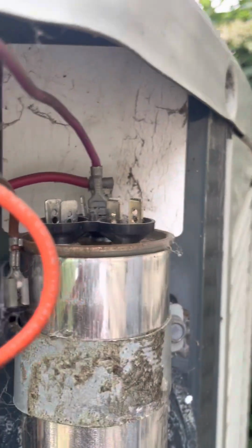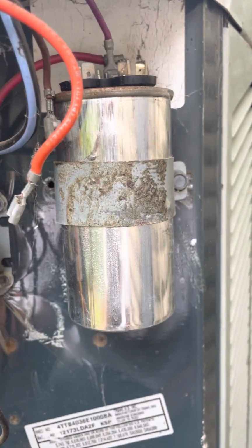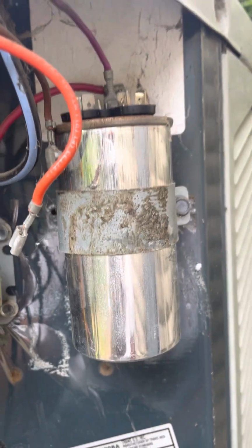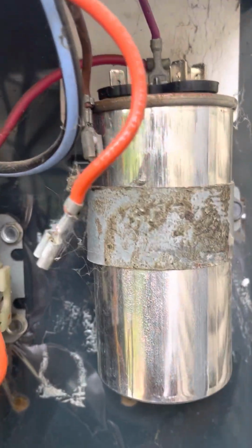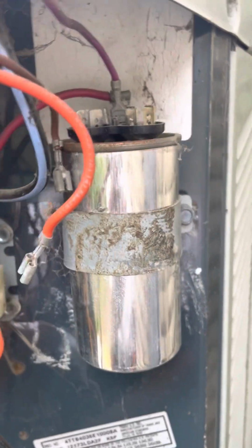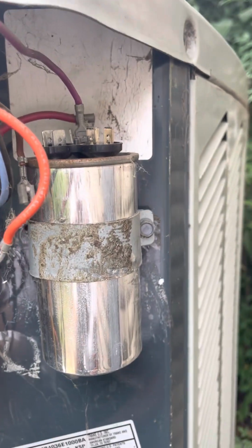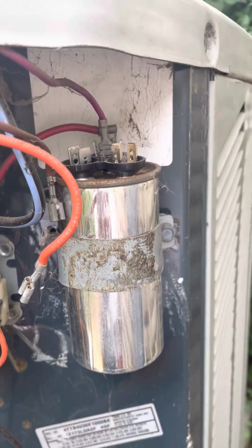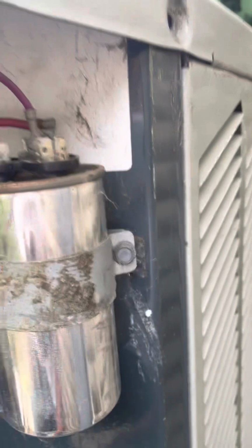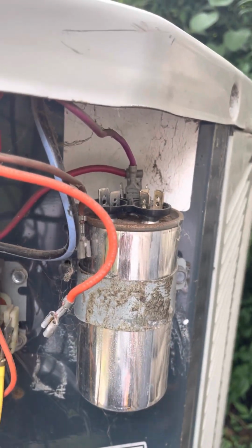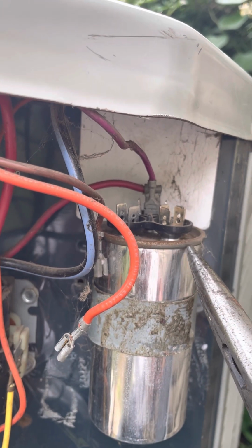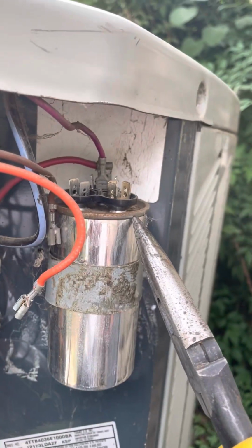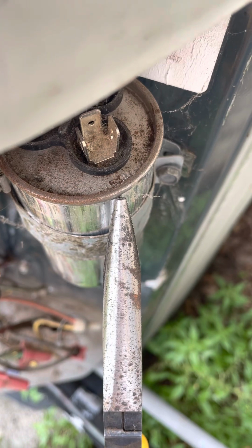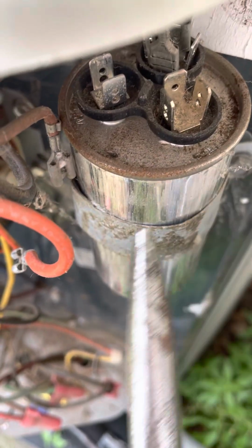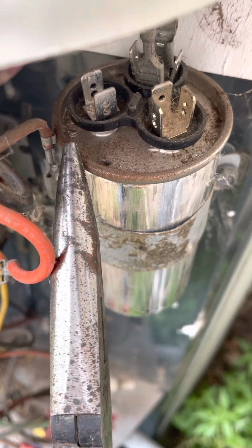Alright, now the wires in the back. This is called a dual run capacitor. It's for both the compressor and the condensing fan motor. So you have a terminal for the fan and a terminal for the compressor, and then the third terminal is the common terminal. This one right here is for the compressor. It's labeled Herm. I'll try to show you guys. I don't know if you can see that, but that's labeled Herm. And as you can see here, that's fan.